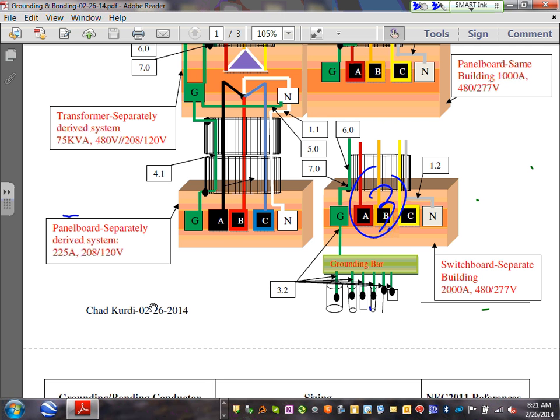And we need to do grounding and bonding at the second building. Okay, so Adam, the second building is 2000 amp. The second building is 2000 amp. Is that the separate building? Yeah, the second building is 2000 amp. We need to size the grounded conductor for it. Never mind. 1.2, the same thing, the grounded conductor. And we need to size the equipment grounding conductor, and we need to size the equipment bonding jumper. Three things: 1, 2, 3. Okay, and the fourth thing, guys, is the grounding electrode conductor.